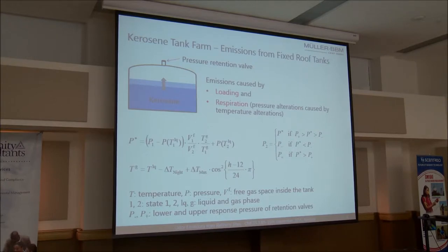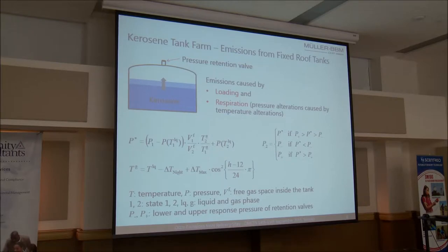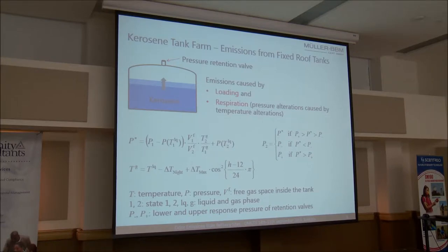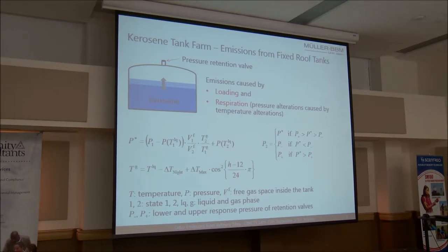The exhaust volume caused by respiration is caused by pressure alterations due to temperature alterations — essentially nothing more than the ideal gas law. The key point is that both the filling level and the storage temperature of a tank are usually available as measured data in very good resolution, which means we can easily calculate emission rate time series of the exhaust volume using simple mathematics and physics.